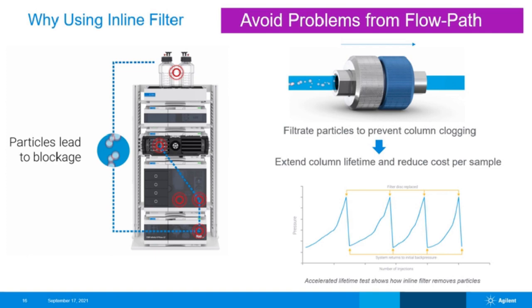The chart at the bottom right shows the result from our accelerated lifetime test. We can see how the pressure increase caused by particles can be quickly and easily eliminated by replacing the filter disc.